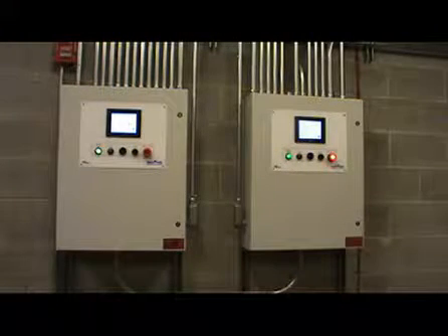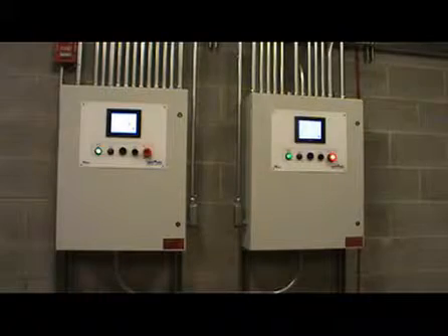A master control system has a single controller that incorporates all system functions. The individual equipment elements are provided without onboard control. All sensors and devices connect to the master controller, which is often designed with dual PLCs and dual power feeds for redundancy.